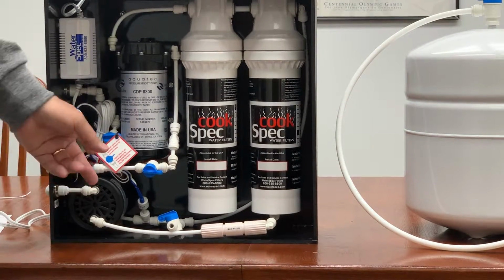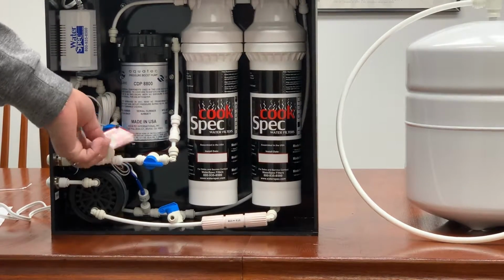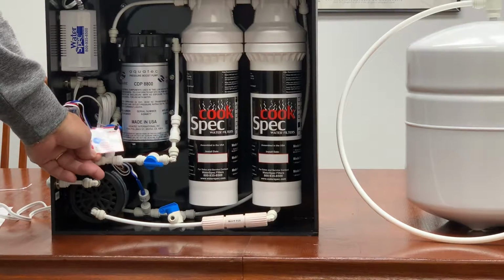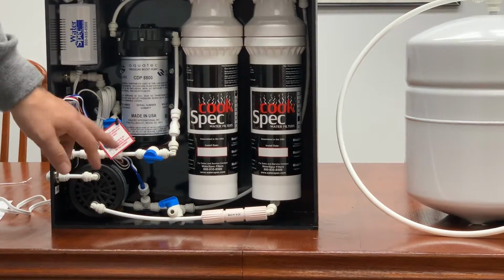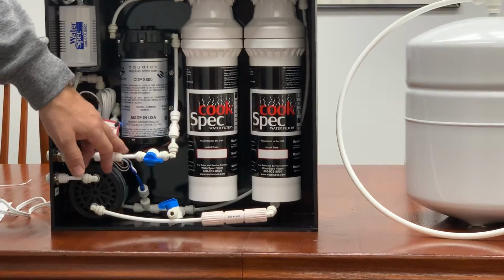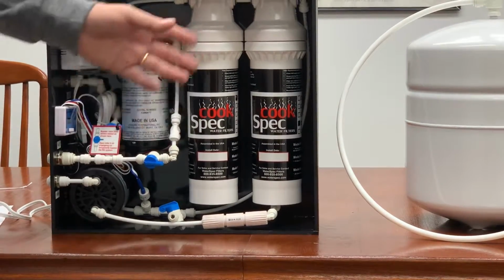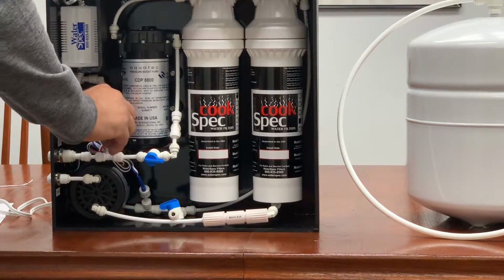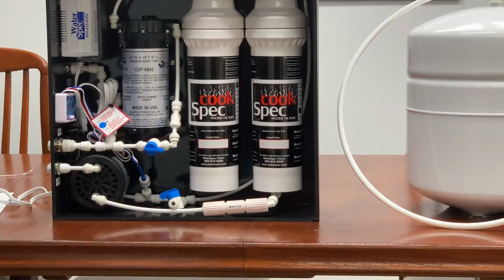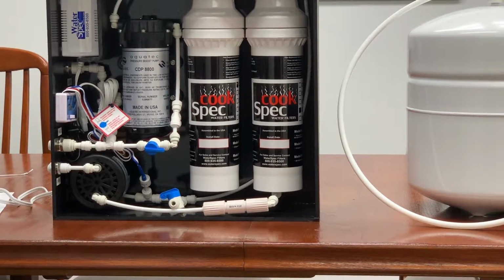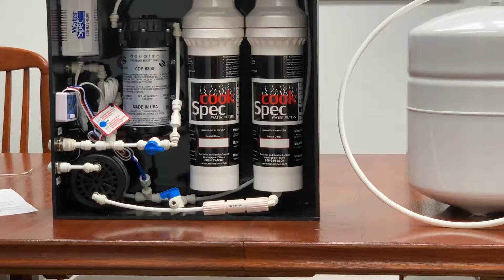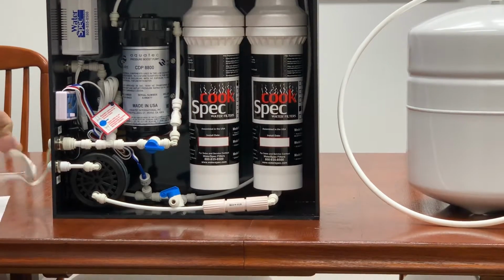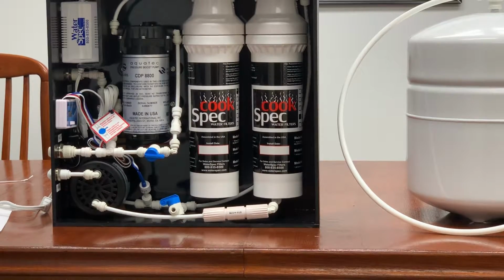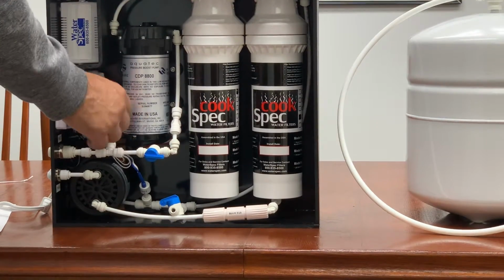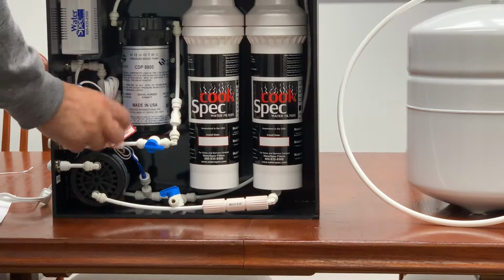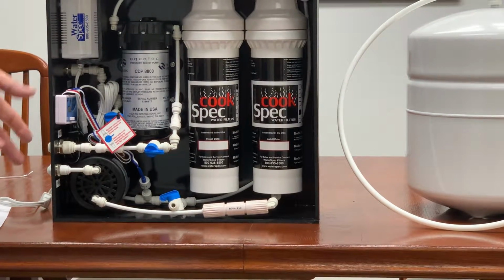One or two other valves you have on the system. This is a bypass valve. Notice it has a tag on it that says only open this during cases of an emergency. So if there is a low water issue and no service personnel out there that can take care of an issue, say with a clogged cartridge or something else, then the manager or personnel can open the bypass, and it basically bypasses the unit completely. It is always best when the unit is bypassed to unplug the transformer so the booster pump does not continue to run. Once service is finished, it is of utmost importance to close the bypass so the equipment is protected.